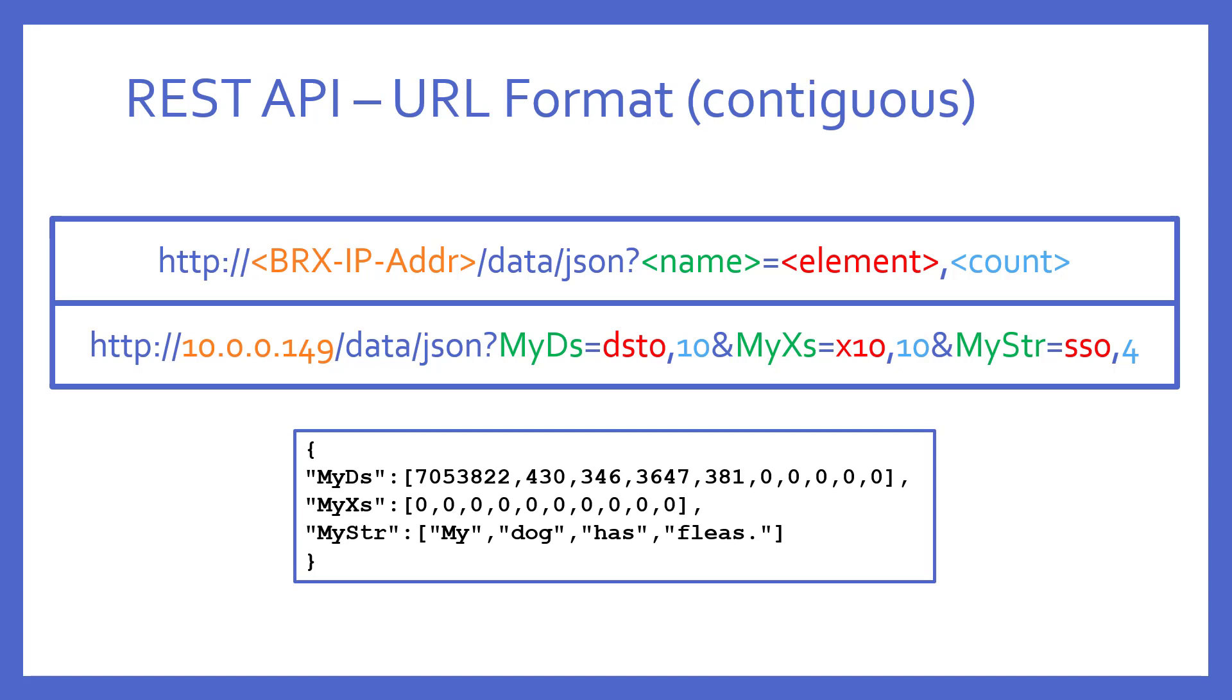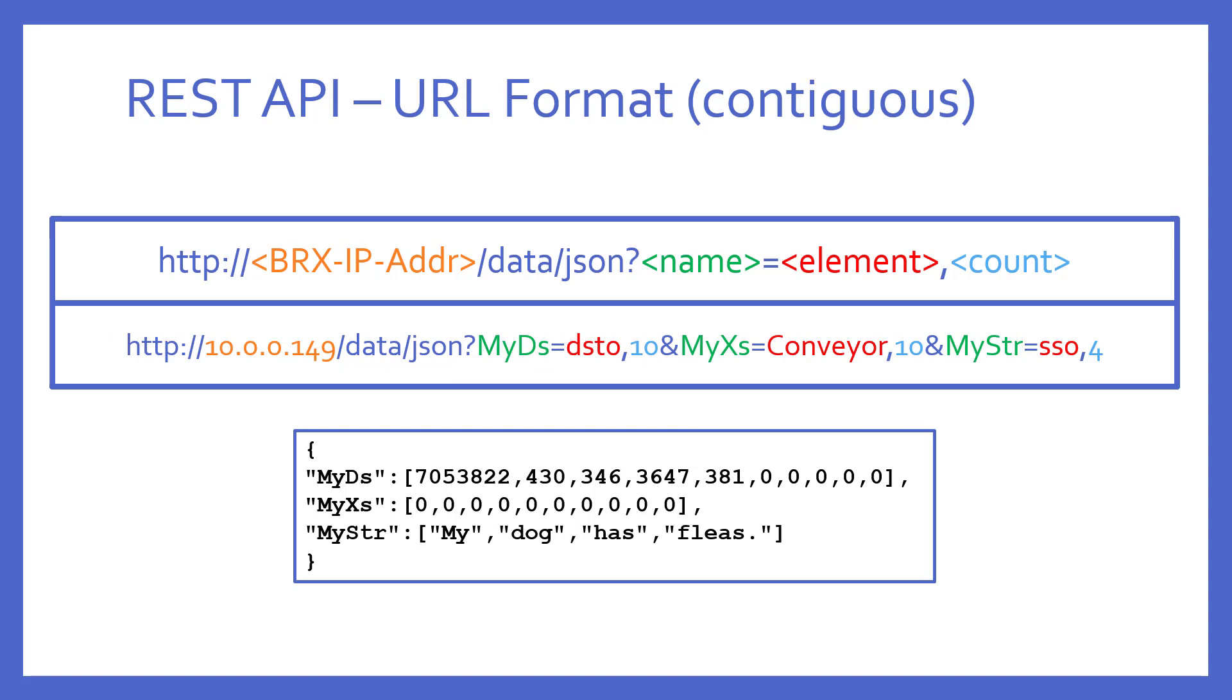The result? This. Notice here that the contiguous values are given in a JSON array. And since I requested three groups of contiguous values by utilizing the ampersand in my request, then the resultant JSON object has these three arrays properly separated by commas. But again, make note. What if my X10 input element had a tag name or a nickname of, let's say, Conveyor? Then, the URL could use the tag name of Conveyor instead of the raw element name of X10. Always keep this in mind.